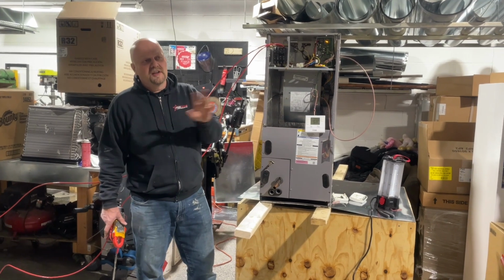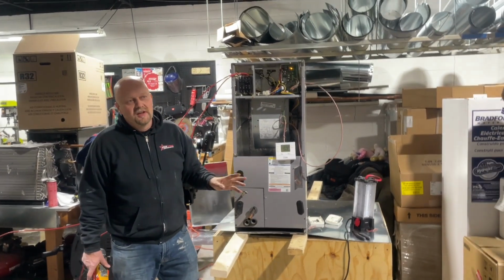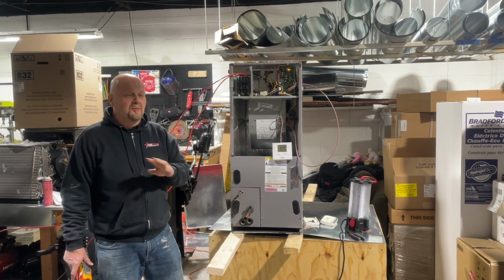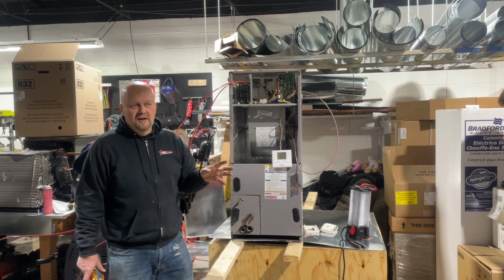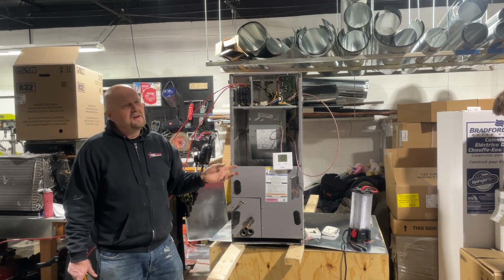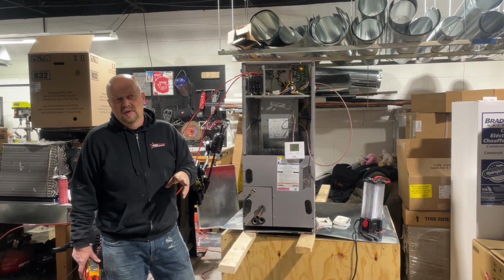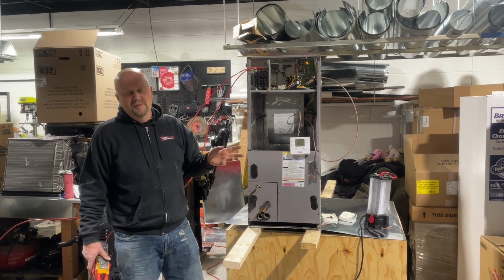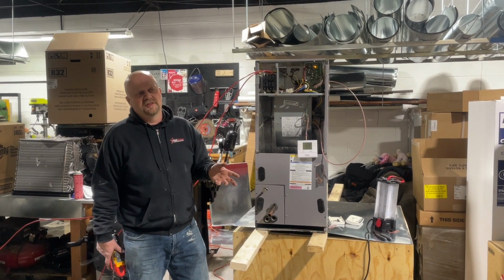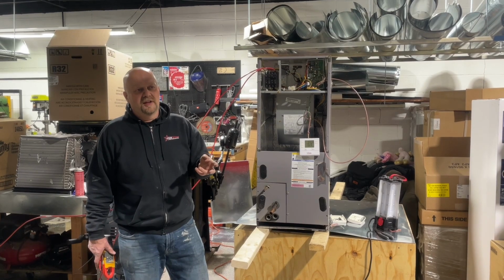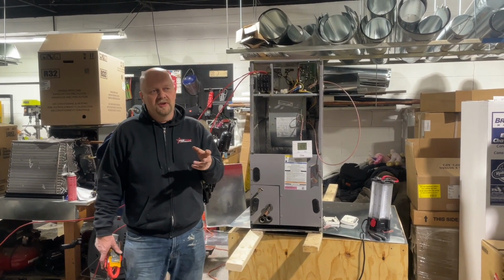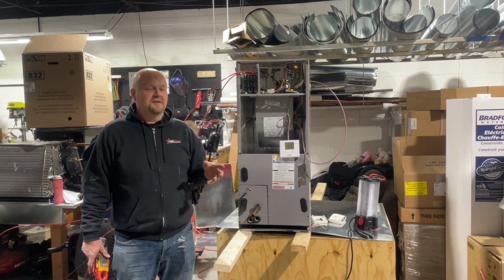Typically, you would start getting pressures of 700 to 800 if the heat pump was able to run. Now, most modern heat pumps will sense the high temperature of the liquid and turn themselves off, right? As an emergency, but older heat pumps didn't have it. Either way, it won't function. That's why we go through the whole setup on our thermostats on EcoBee to make sure that only one can run at the same time.